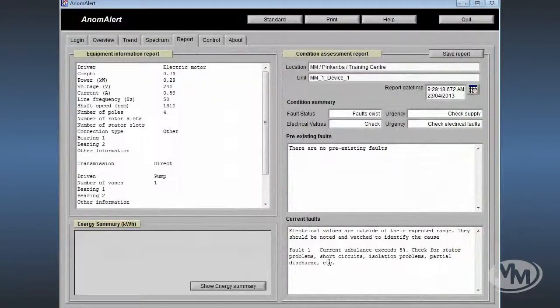Now back on the reports page of the Anomalert software, it can be seen that one fault has been reported. This is described by the unit as a current imbalance exceeding 5%.